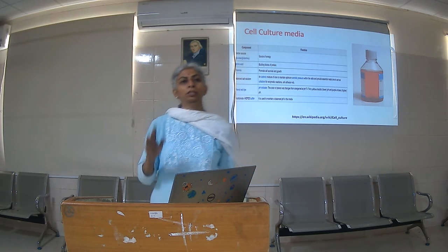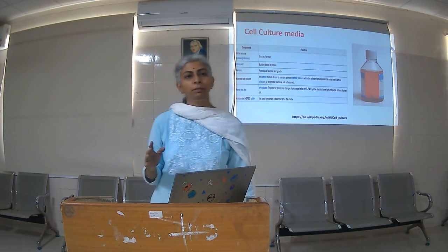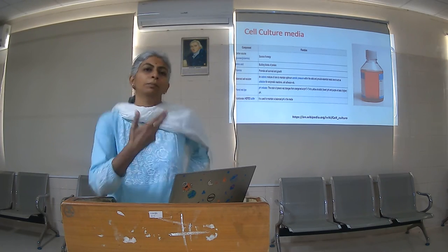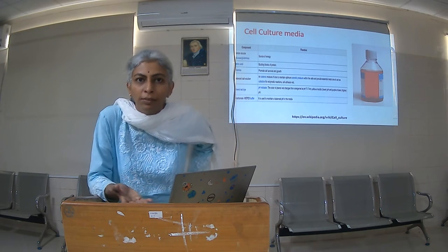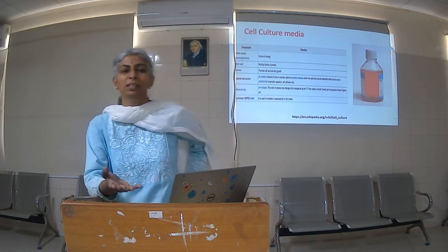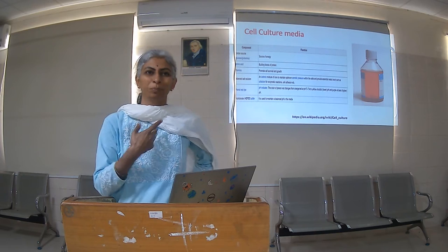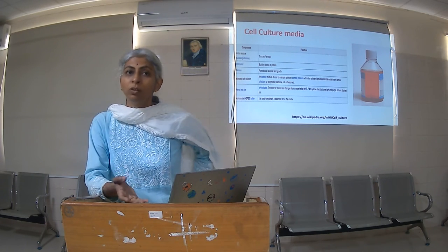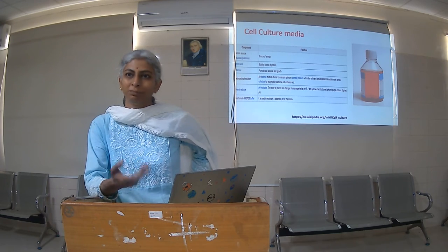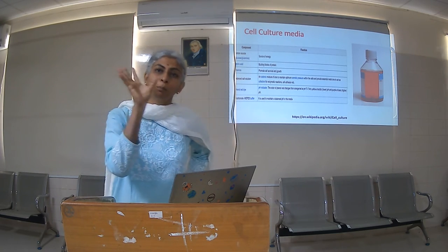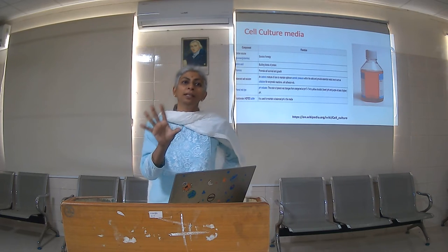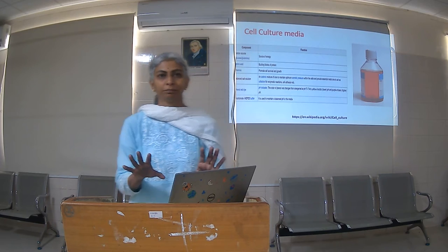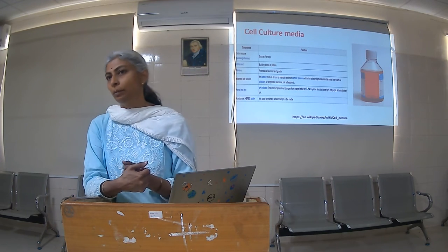CO2 इंक्यूबेटर में एक और चीज मेंटेन होती है, वो है रिलेटिव ह्यूमिडिटी. सो सेल कल्चर अगर आप बहुत देर तक, अगर आप ह्यूमन या वर्टिब्रेट देखेंगे तो 37 डिग्री सेंटीग्रेड पर रखना पड़ेगा. 37 इज एक्चुअली हम लोग ही, you know, we perspire so much. So 37 degrees centigrade is good enough to cause the media to start evaporating. So you maintain the water content or the relative humidity in the incubator by keeping some sterile water inside so that this phenomena does not happen.